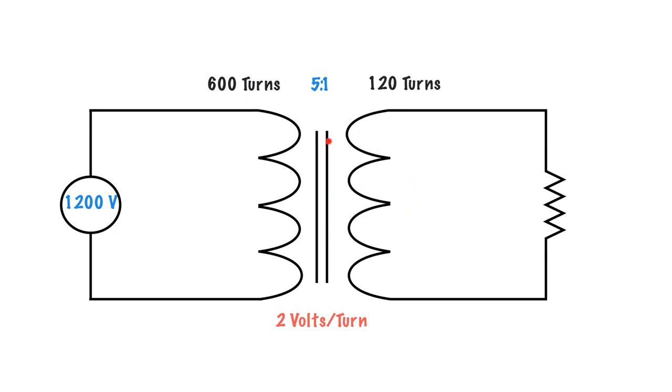The lines of inductance are being cut over on this side, and so we're getting the same volts per turn on the secondary side. So 2 volts per turn that we use to calculate it off the primary, 2 volts per turn times 120 turns will give me my secondary voltage, which is 240 volts. So that's the volts per turn method.